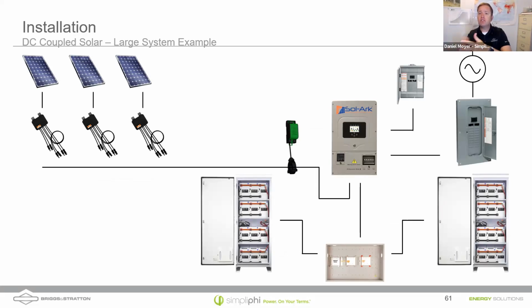What do we got here? We got solar, some DC coupled solar. These look like microinverters, but they're not - they're Tigos, because here's a Tigo transmitter. We're feeding DC into the Sol-Ark. The Sol-Ark is feeding DC right out through those MPPT charge controllers, keeping these battery banks properly charged. Here's where we're combining the battery banks. Here's our critical loads panel, here's our non-backed up loads panel, and here is grid. Kind of a bread and butter system.